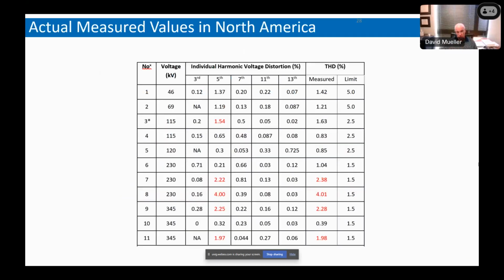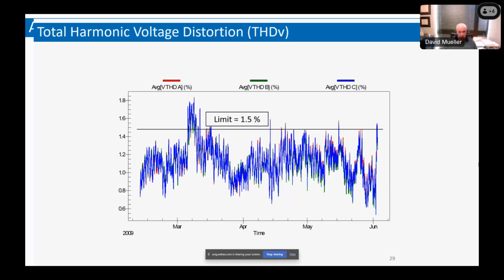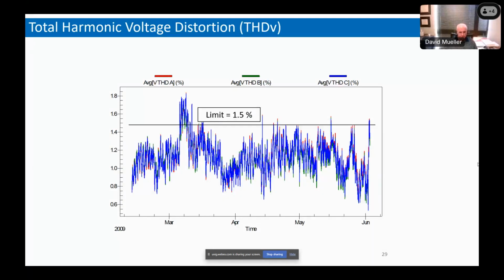When I tried to convince the 519 working group that I'm part of that we ought to change these limits, I said, hey, we've got a bunch of experience at a bunch of places where we just can't meet the limits. Particularly the fifth harmonic voltage limit is typically a problem in a lot of sites. But anyway, the limits are what they are. They didn't get changed.